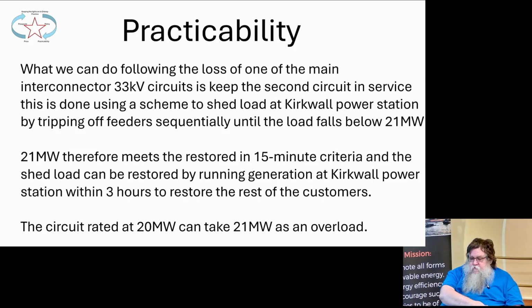So how does Orkney keep it going when one of the 33 kV circuits trips? If you're not running the power station at the time, and all the embedded generation is off, there's no wind turbines running, you get one tripping, the other one's going to overload. There's a scheme in place that detects the overload, sends some signals to Kirkwall, and very quickly trips off circuits in Kirkwall, just enough to bring the load down to less than 21 megawatts. That scheme has been in place since 1998 or 99, I can't remember exactly. And that's what keeps the lights on for the vast majority of people.